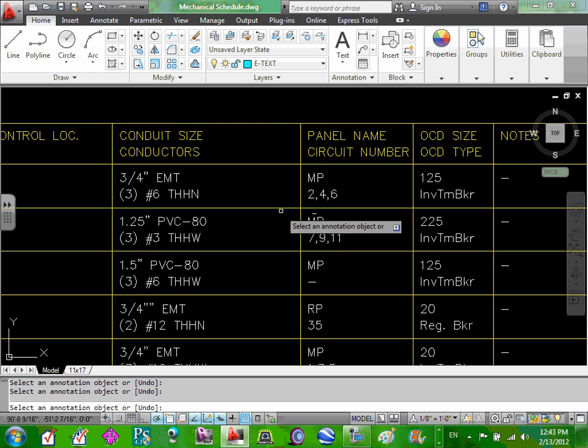You can circuit them. There's a few of them that are going to be from the main panel. The rest of them are going to be from the receptacle panel. So, air handling unit, condensing unit, boiler pump 2, all these are going to be from the mechanical panel. Why? Because the sheet is telling you this on page 11. The 2 pumps and the 2 chillers, only from the mechanical panel. Everything else is what? Receptacle panel.